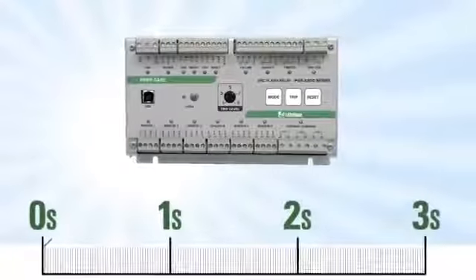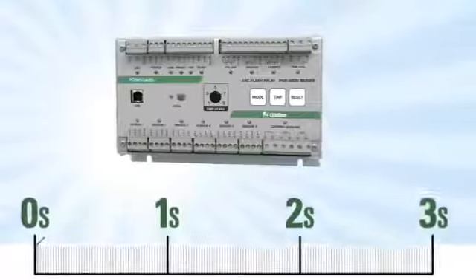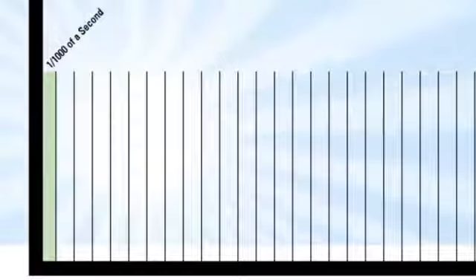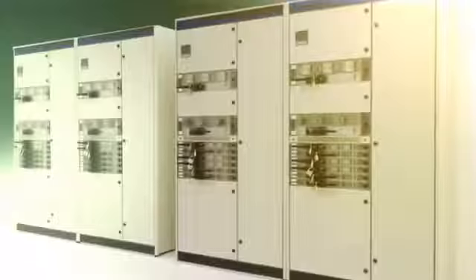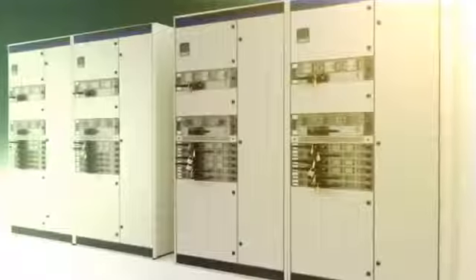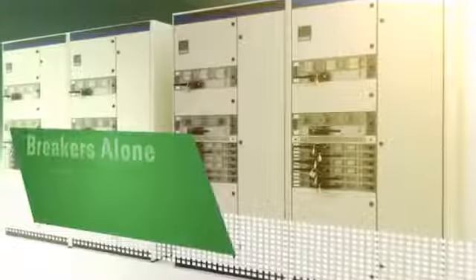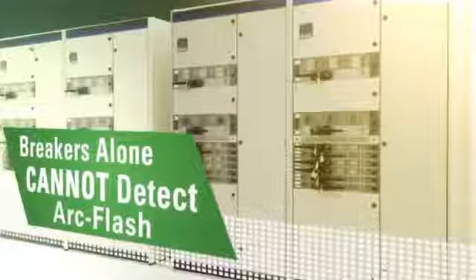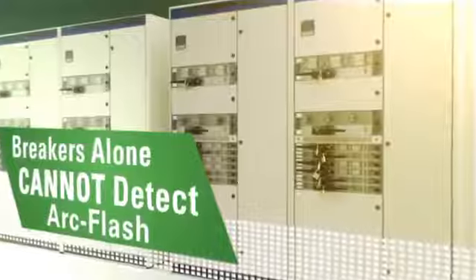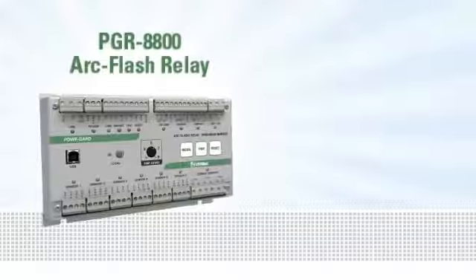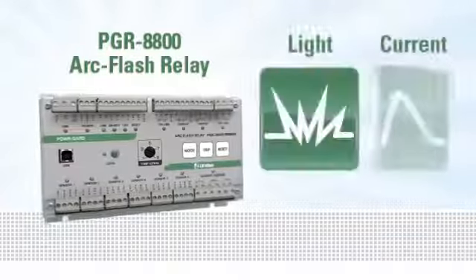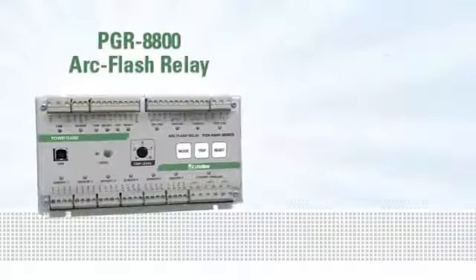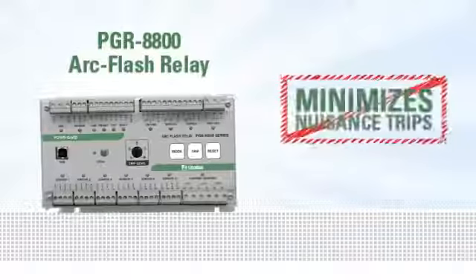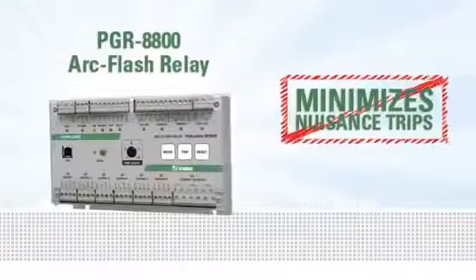The Littelfuse Arc-Flash Relay detects and trips a fault extremely fast, in just 1/1000th of a second, before significant damage occurs. Because the early stages of an arc flash draw a fraction of bolted fault current, circuit breakers alone cannot distinguish between the arcing current and a typical inrush current. So, the PGR-8800 solves this problem by detecting both light and current. It provides superior arc flash protection while minimizing nuisance trips.